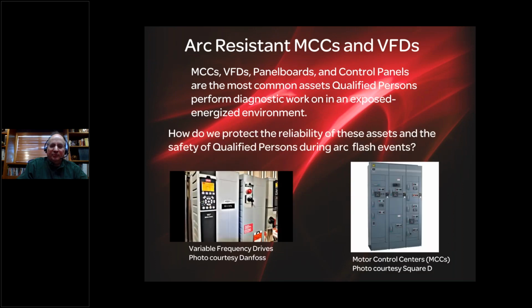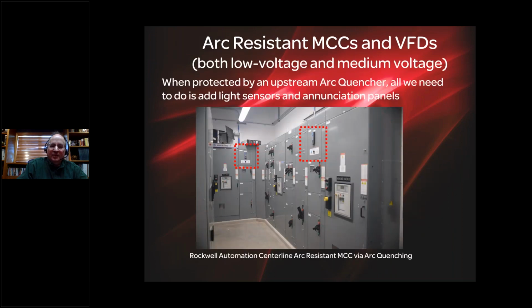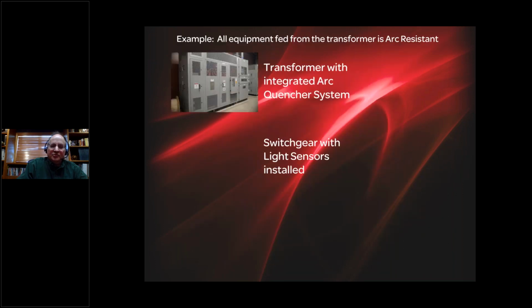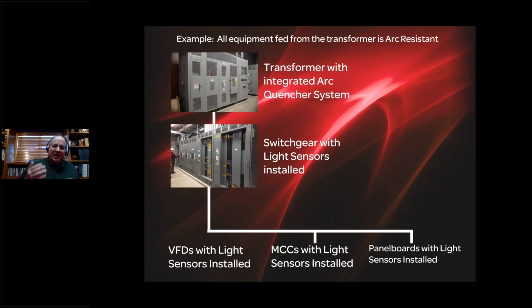As long as the switchboard is extended to right here, this is what I'm looking for. As long as that switchboard is like the switchboard here, those are UL 489 breakers. I can tell that's an I-line, Square D I-line stack, exactly what you described. So as long as we have an arc quencher protecting that system, as soon as I extend my light sensors into that switchboard back to the arc quencher system, that switchboard becomes arc resistant.